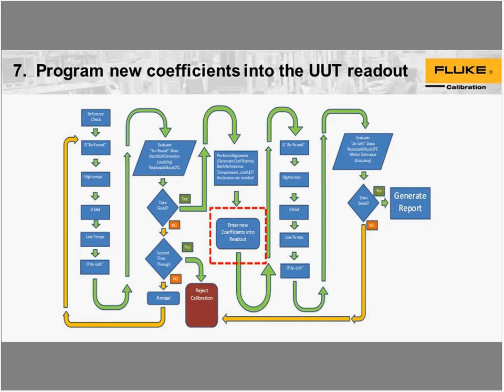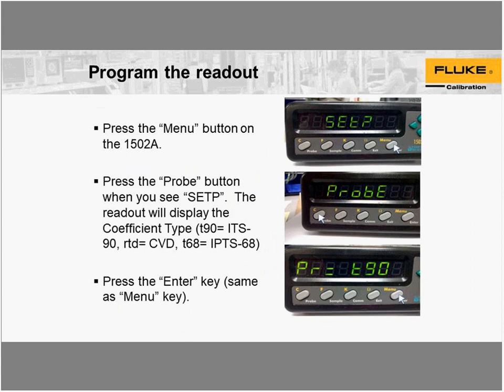Once we have those coefficients, we need to enter them into the readout. So on a 1502A, it's rather easy. You press the probe button, which is the far left button, and you'll see probe on the display. Then it'll indicate PT or PR equals T90 rather, using the ITS-90 coefficients. If you happen to have CVD coefficients or IPTS-68, that option is also available. But we stick with ITS-90 because they're the most accurate coefficients.